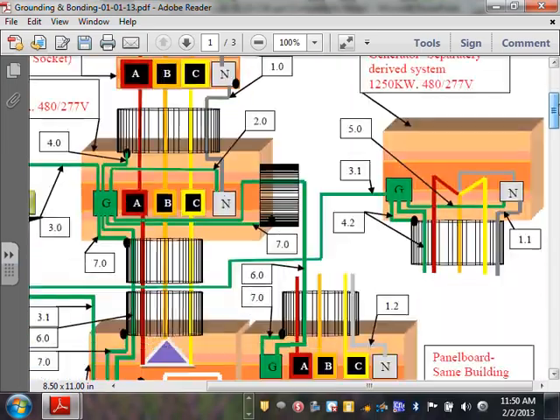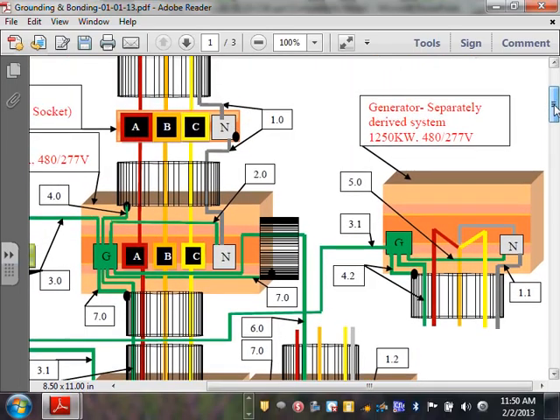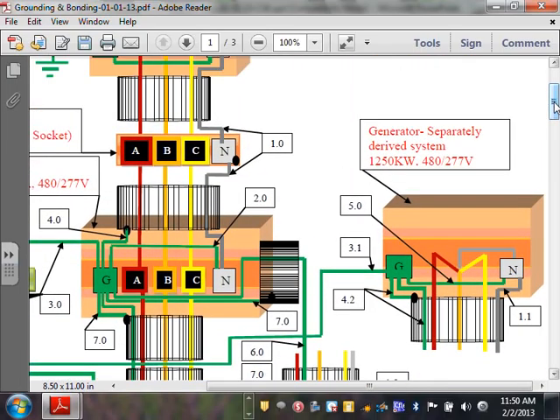So, the last one on this sheet, I hope it's making sense for you guys. The last one is a generator. So here's my generator. I picked a big fat boy. This is a 1250 kW 480/277 generator. I'm running it as a separately derived system. You have to decide: are you going to run a separately derived system or a non-separately derived system?